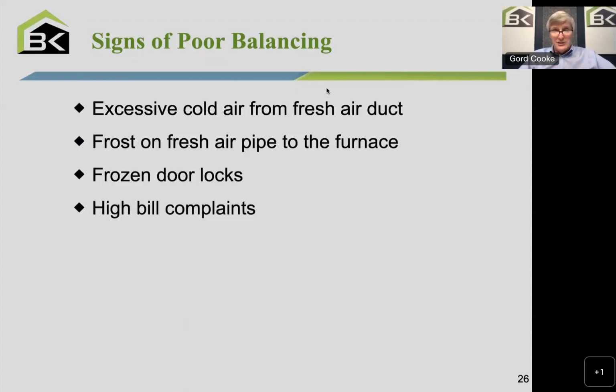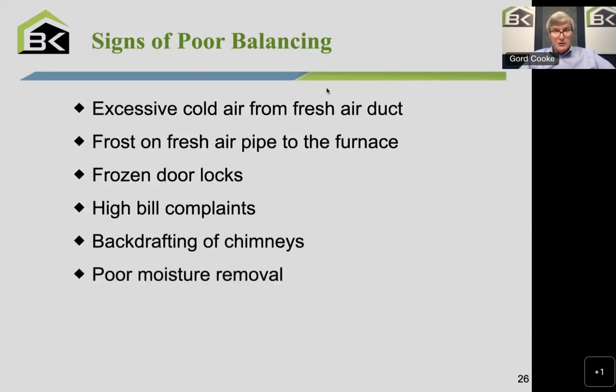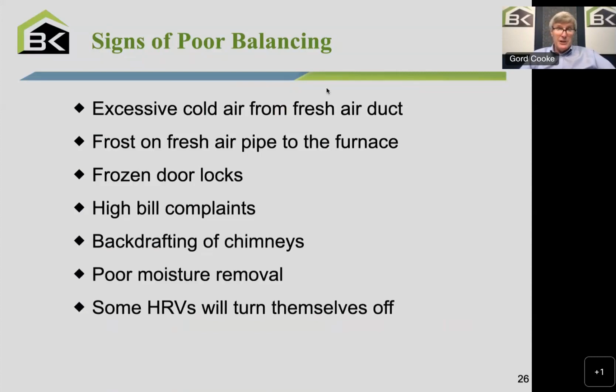But if they all of a sudden see extraordinarily much higher bills than they're used to, that could mean the unit's out of balance. Something's happened within the unit, dampers have moved or something, and the unit's not correctly balanced. Or if you're getting constant backdrafting of chimneys, that could mean the unit's not balanced correctly. Or again, if you don't get proper moisture control, the unit's worked fine for years, now all of a sudden they have condensation problems on their windows. I wonder if the HRV is not working correctly. And sometimes with HRVs, if the defrost isn't working correctly or balancing correctly, it'll actually turn itself off.